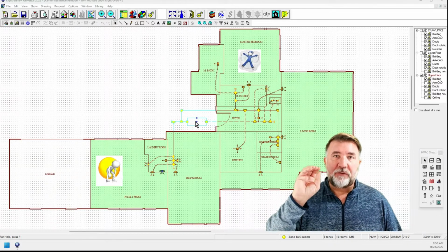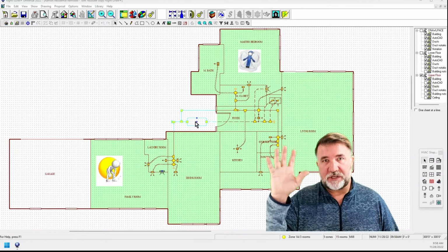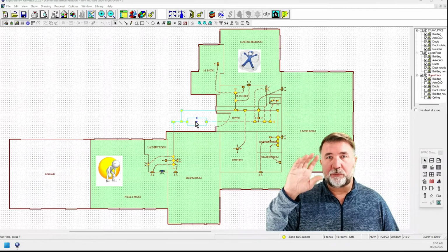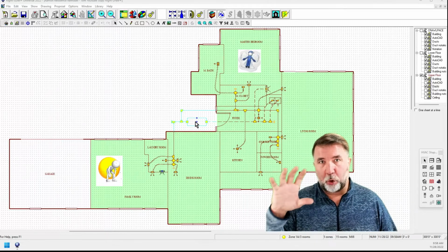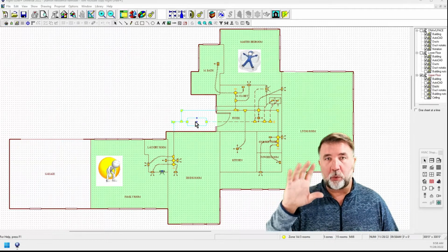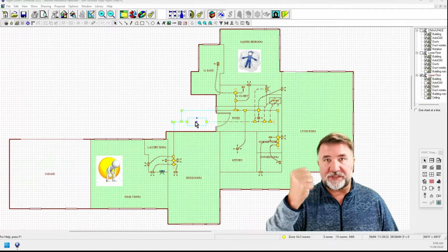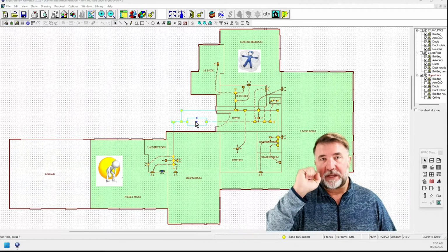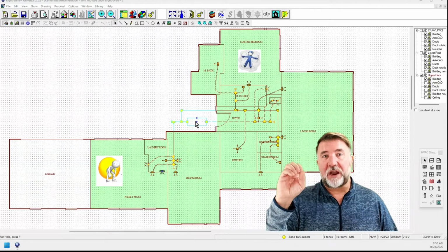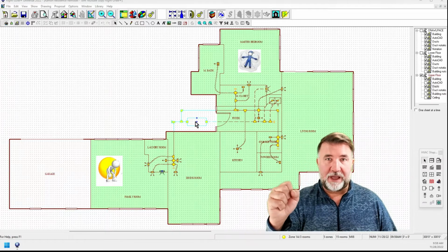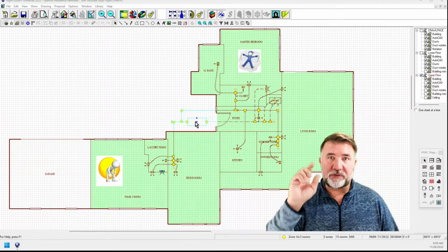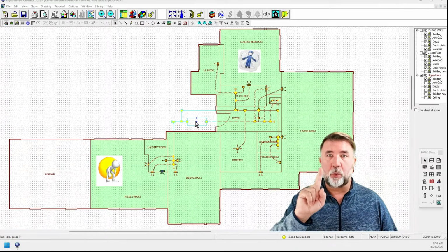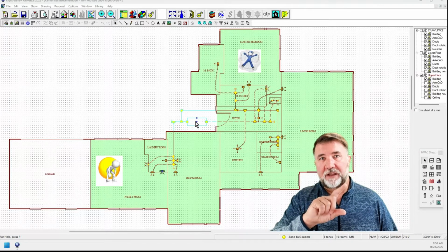And if you oversize the system, it blows so much cold air into the house so quickly, or I should say, it removes heat so quickly with the vast amount of air it's running through and dumps it back into the house. It drops the temperature so quickly that the thermostat is satisfied.